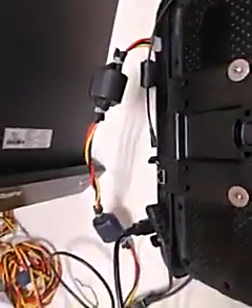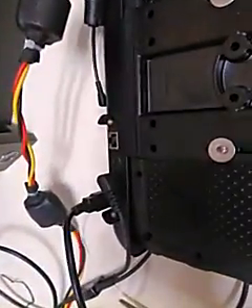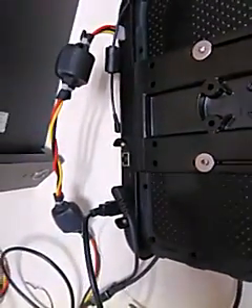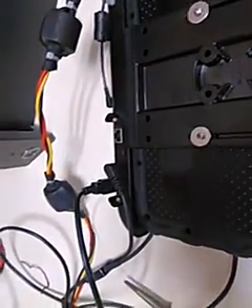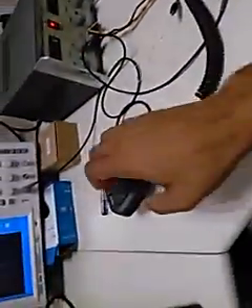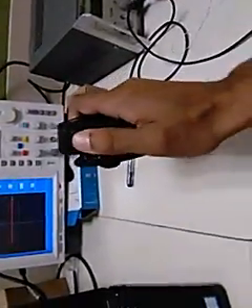I'm testing on a production unit and production cradle. The test case will include insertion of all the connection points one by one. Right now, only the 3.5 mm jack is connected, which is the RSM. The USB cable is connected, but it's not linked anywhere. So right now, I would be pressing the PTT button.